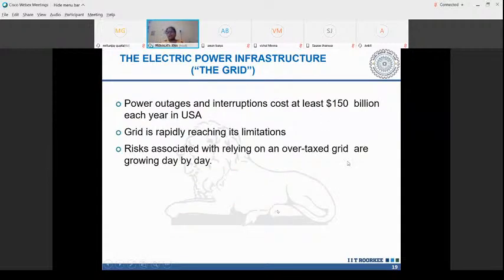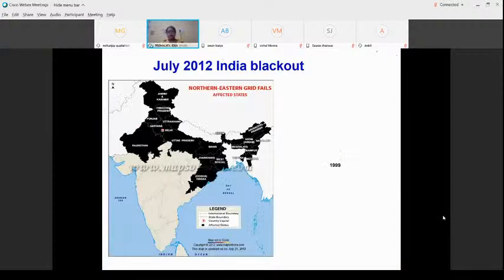So the second disadvantage I'll put in front of you is the blackout. In power outages in India, in 2012 there was a national grid blackout. And let me tell you, just for 2 minutes, what this blackout is. Maybe the term is new to all of you, and you can also know it. On the night of July 30th, 2012, there was a line connecting Bina to Gwalior. Bina is on the northern side, Gwalior on the western side, and in between the north and west side there was a 400 kV line which was overloaded due to the excess power drawn from the northern side customers.